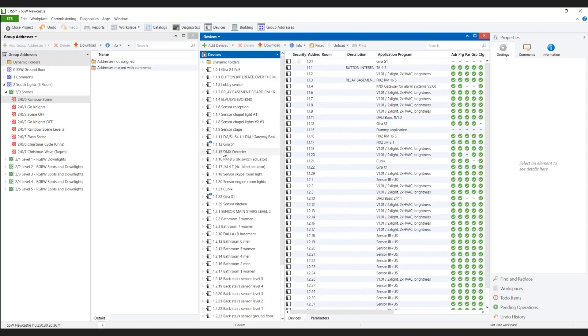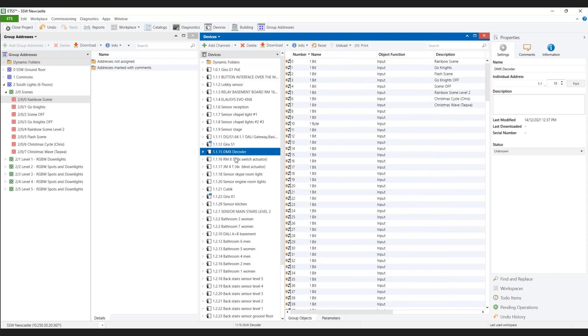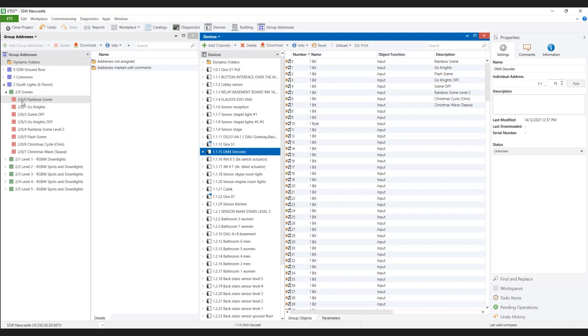Not as yet. So what we have to do is pick out the DMX decoder which I have here, which I've added. So if I pick on that and open that tab up now within here, I've attached it to an output. Now output for rainbow scene is output zero. So now we're attached to something. So now that that group address is attached to our DMX configurator. And this knows that once that group address has been triggered, that's going to trigger our input within DMX configurator.